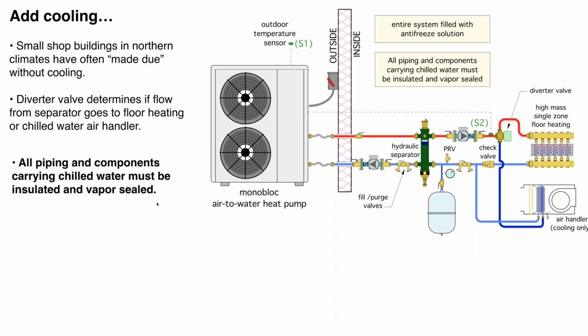So we can add an air handler and a circuit on the right side there. And you'll see I've just shown a diverter valve. Now you would have to make sure the flow capacity of that diverter valve is large enough. It's probably going to be larger than a zone valve, depending on what the flow rates are. But if you're dealing with 10 to 12 gallons per minute of flow, you would need a Cv up in that range for a reasonably low pressure drop. And you can see the idea. The diverter valve simply sends heated water to the floor slab in winter, and it redirects the chilled water flow to the coil in the air handler.